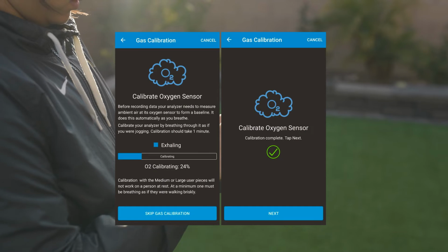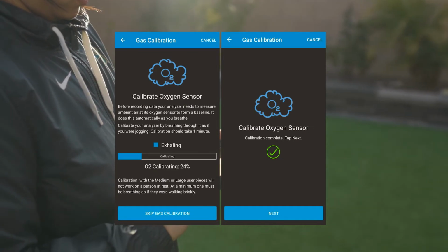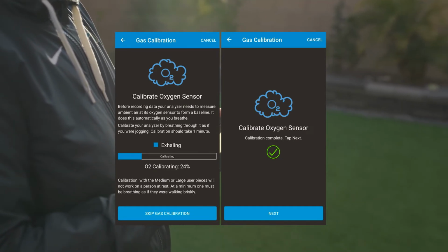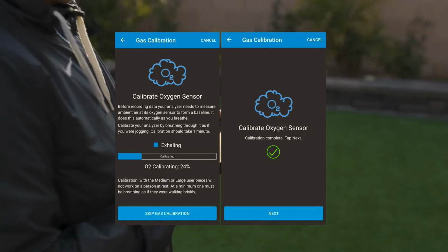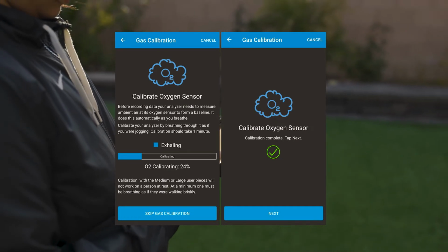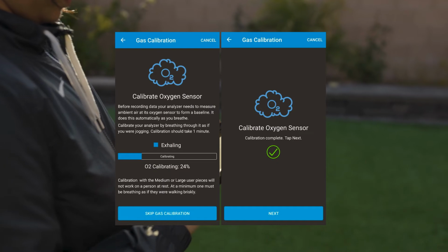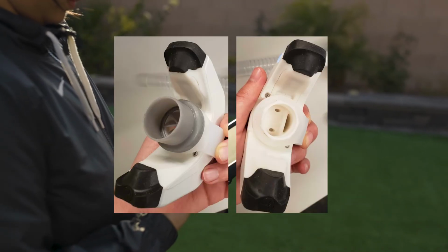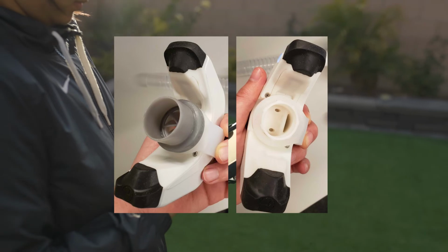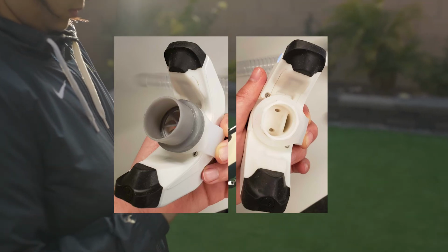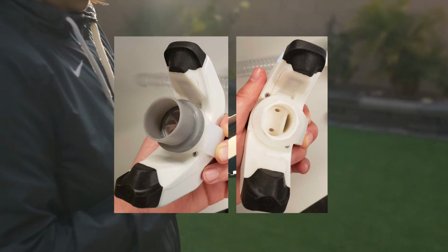For the gas calibration, again, pump the syringe at a rate of approximately 20 strokes per minute. Flow and gas calibration is complete when a green check mark is displayed, and you can tap the next button to continue. Remove the user piece adapter from the shock dampening hose and remove the silicone seal. Once calibration is complete, you are ready to start testing.